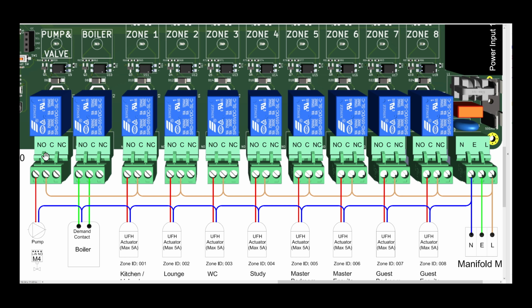In addition, we have another relay that whenever the heat source is demanded and the boiler demand is on, the pump and valve, which are on the floor heating manifold, will also operate. Sometimes there's no valve, there's only a pump. Sometimes there's no pump and no valve, and it relies on the main pump. But most underfloor heating systems have a pump, and this is connected to power the pump.